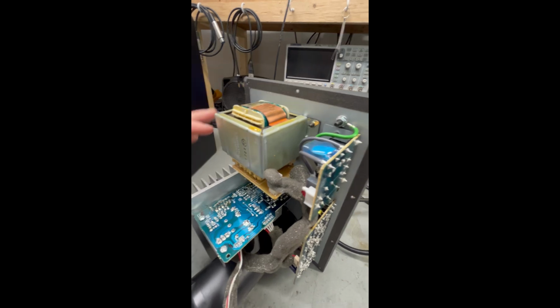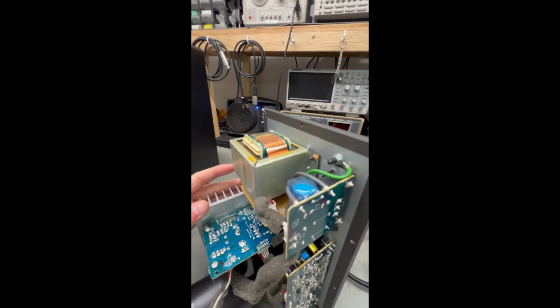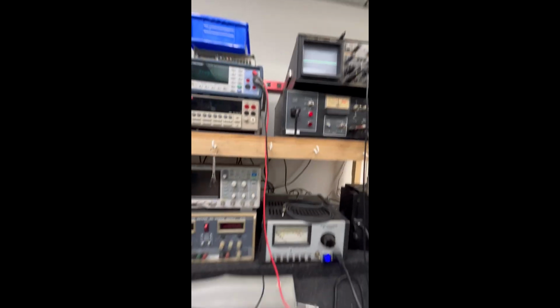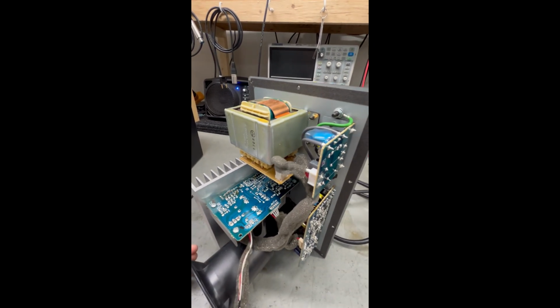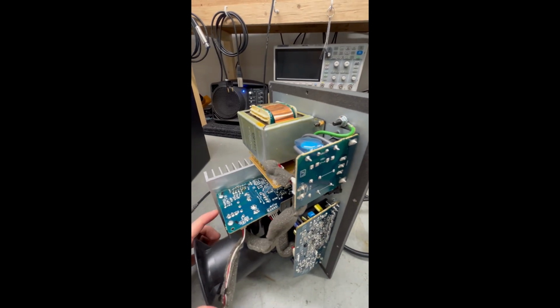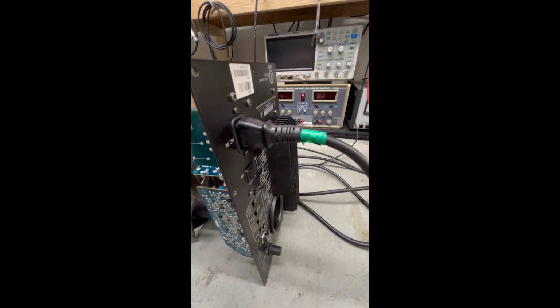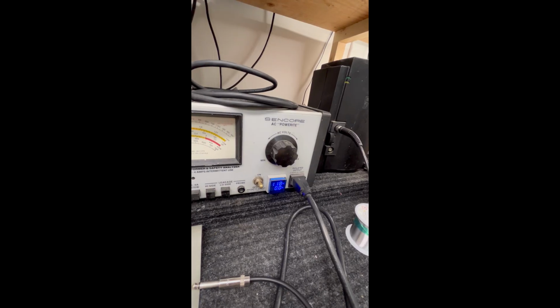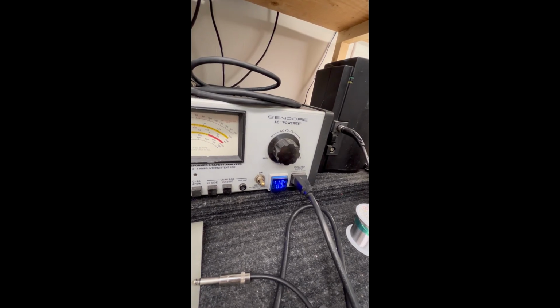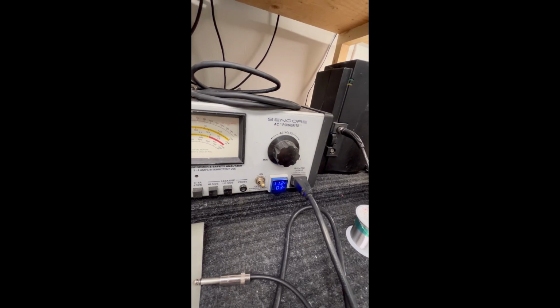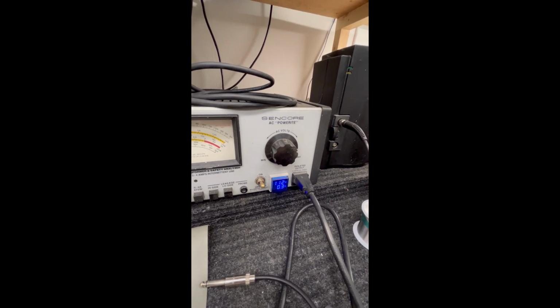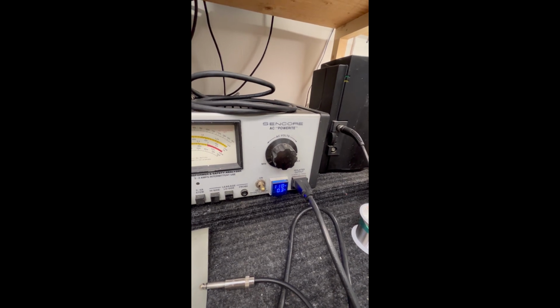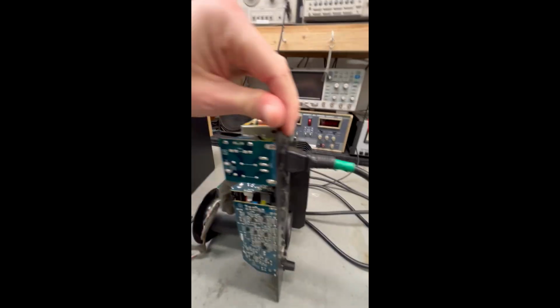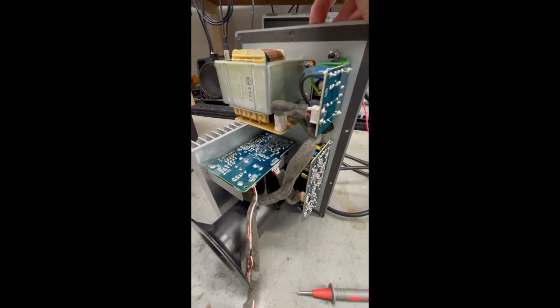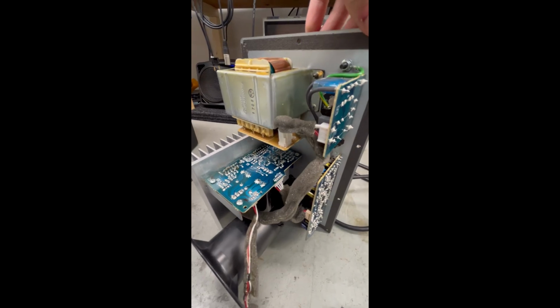There's a big transformer. We don't have to worry about it. If you have this on limit setting and you're trying to work on a switch mode power supply, 90% of the time it's not going to operate correctly. So anyhow, in this situation we'll be okay. So we can actually just turn the device on here, and we can review the amount of current that it's pulling. On limit, it looks like it's pulling about 0.3 amps, so 300 milliamps. I'm just going to switch it over to on. So that's a good sign. It means that the device is actually sinking current right now, and we can continue troubleshooting.